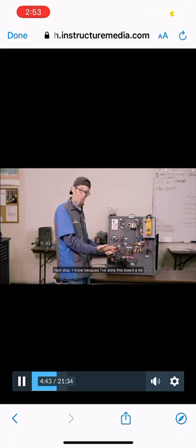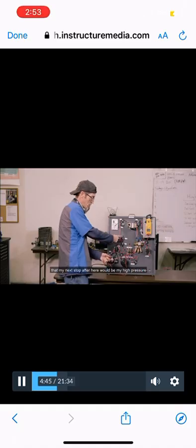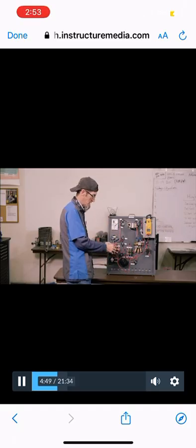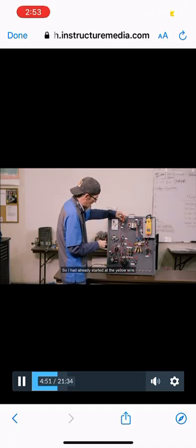I know, because I've done this board a lot, that my next stop after here would be my high pressure and my low pressure switch, because those are the next things on that circuit. I had already started at the yellow wire, so I'm going to go back to common here and go to my high pressure switch. I should see some voltage going into that spot. And I do, which is good. So I want to see it coming out the other side. That would confirm to me that my high pressure switch is closed and still operating.